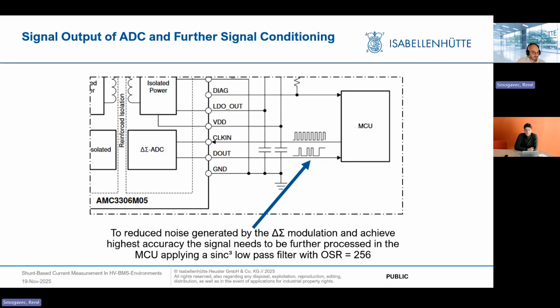And if we zoom further in, we see where the signal is going into the microcontroller unit. To ensure the best noise reduction, we would really advise using a Sinc3 low-pass filter and an oversampling ratio of 256, which is mostly the highest you can go with, and the one that results in the highest settling time, unfortunately, but it yields the highest effective number of bits for a clear signal. So this ENOB value is tied to the signal-to-noise ratio, and thus is a good metric for the value of noise reduction. Delta-sigma modulation, by the way, is a type of ADC that oversamples and noise shapes using a modulation and digital filter.